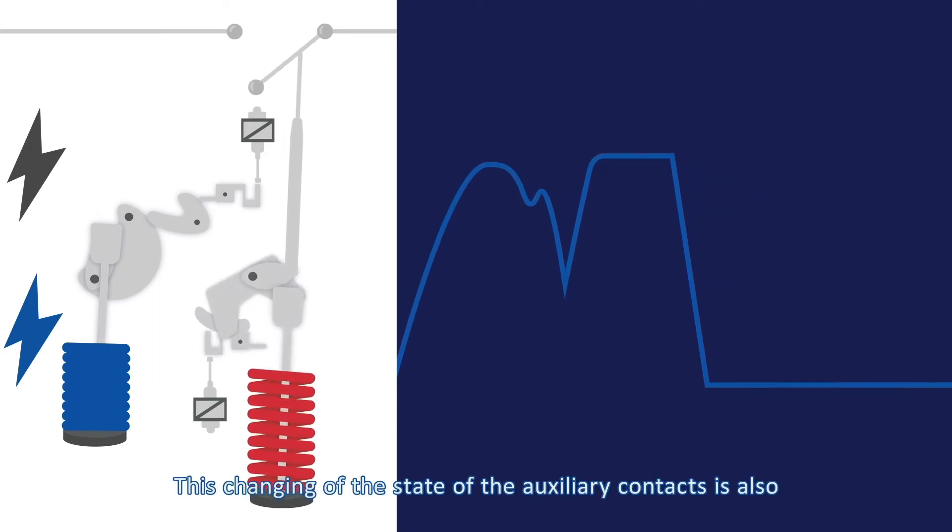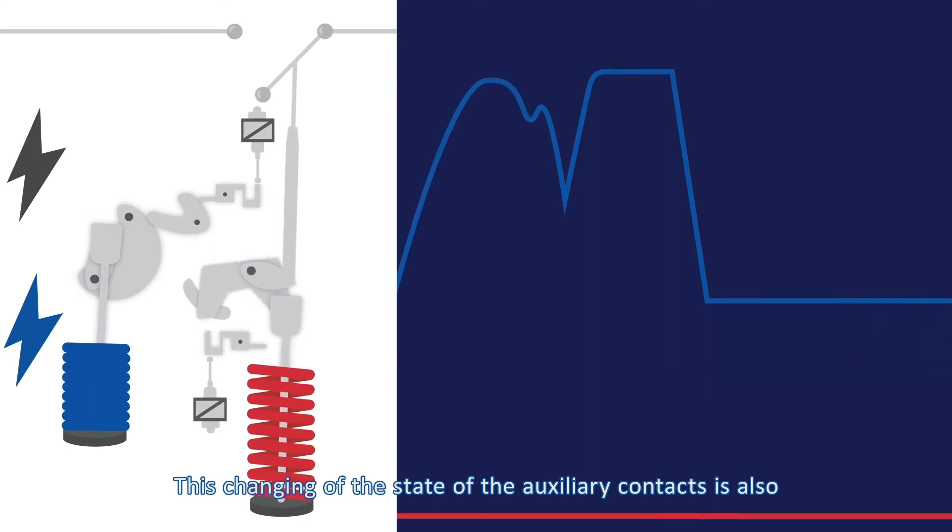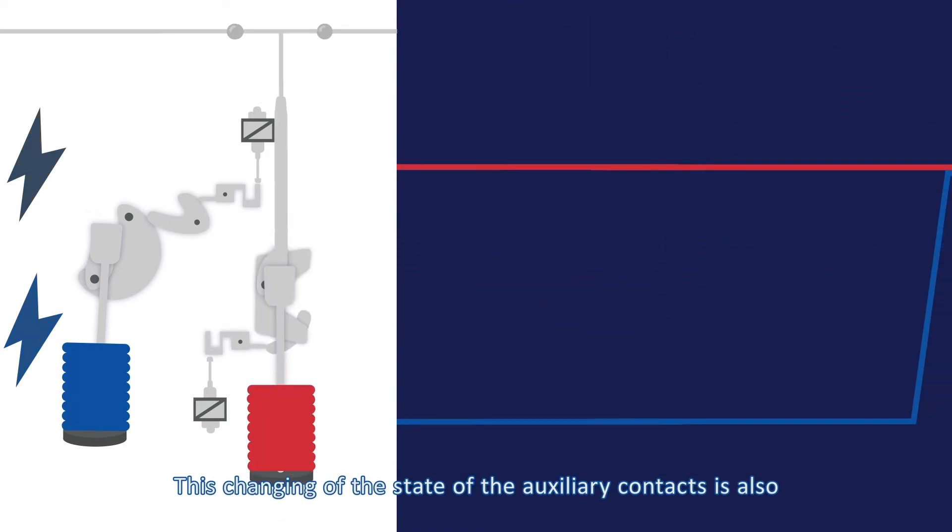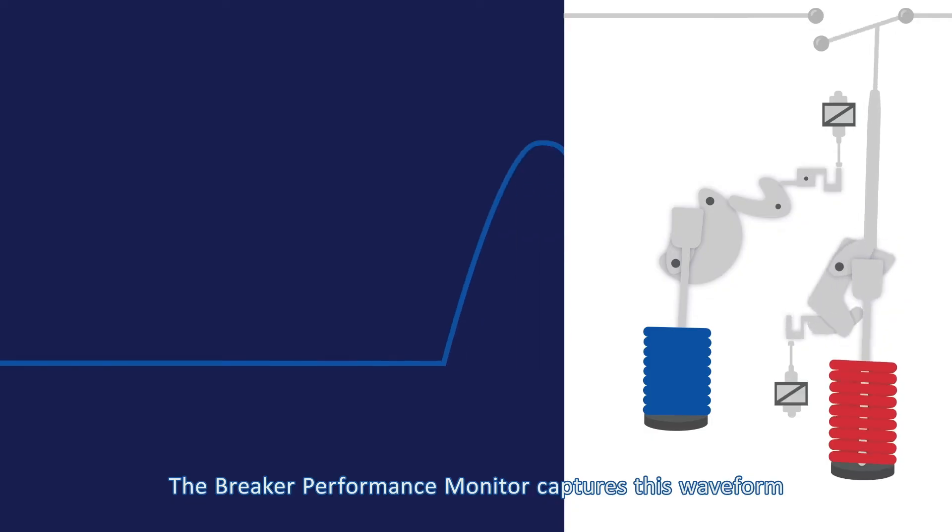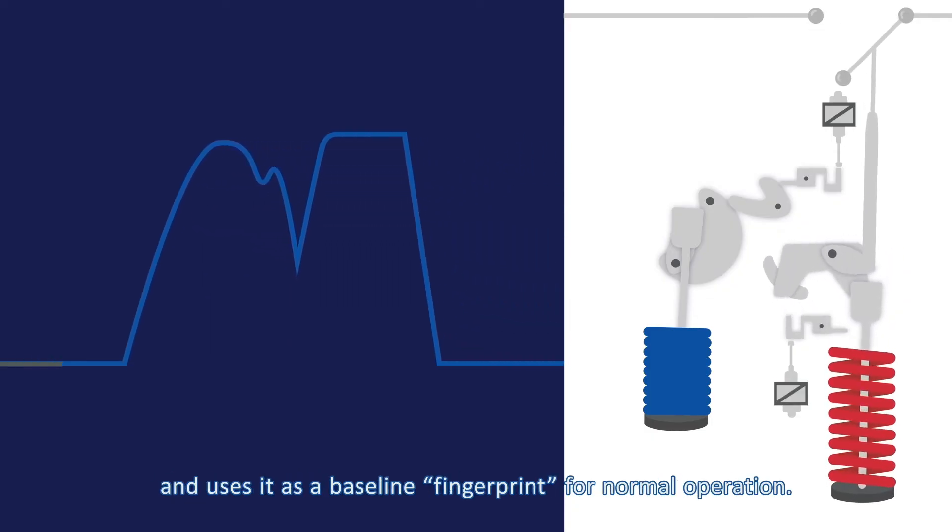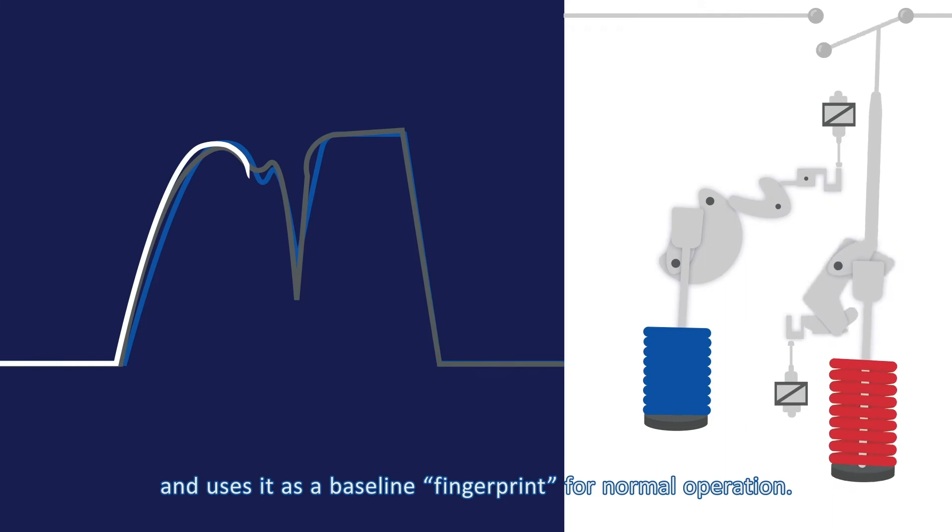This changing of the state of the auxiliary contacts is also captured during the waveform capture, as well as the current flow through the breaker's main contacts. The breaker performance monitor captures this waveform and uses it as a baseline fingerprint for normal operation.